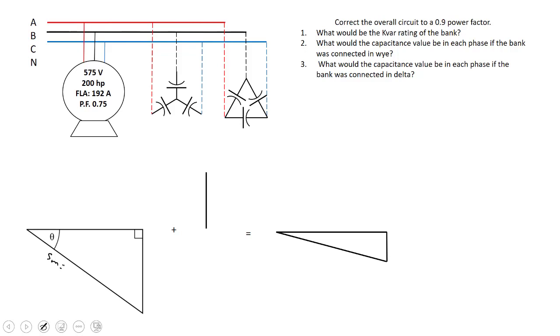The best bet in this case is to figure out the apparent power of that motor by using V line times I line times root 3. So if I did that I would take 575 times 192 amps times root 3. We're looking at about 191,218 VA.